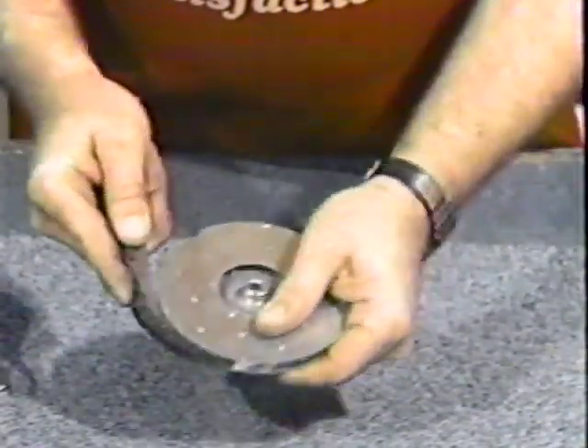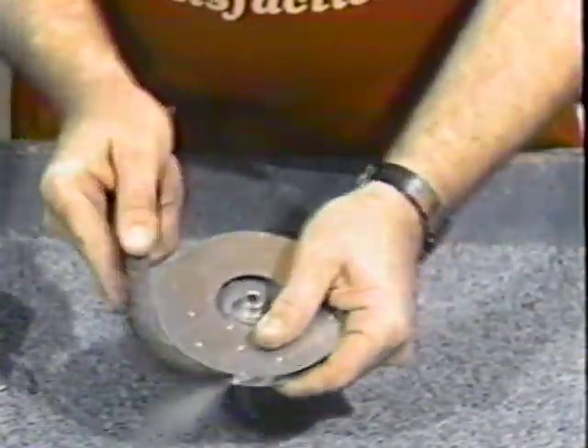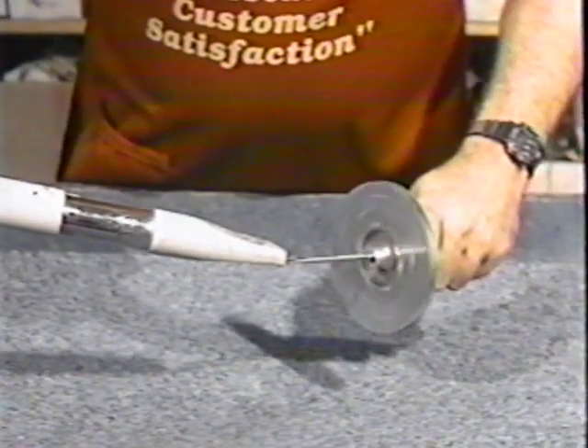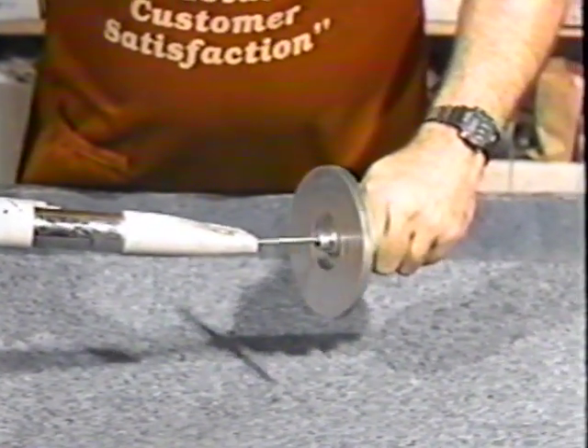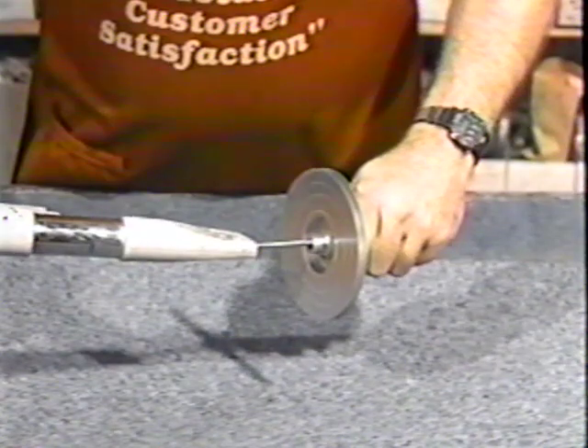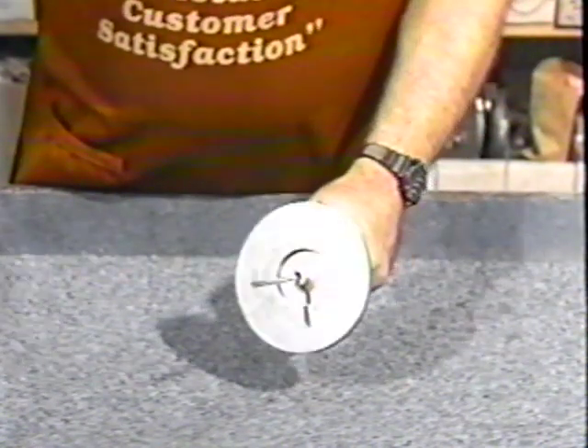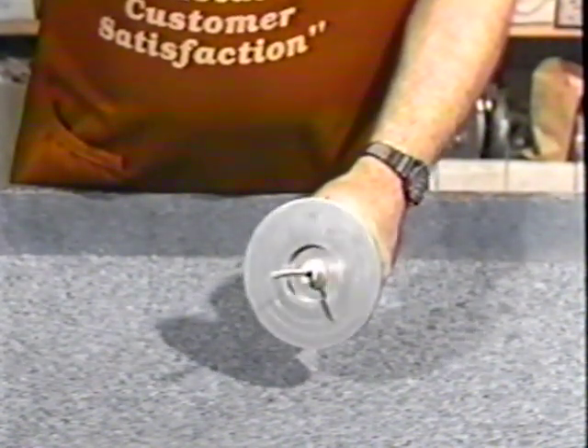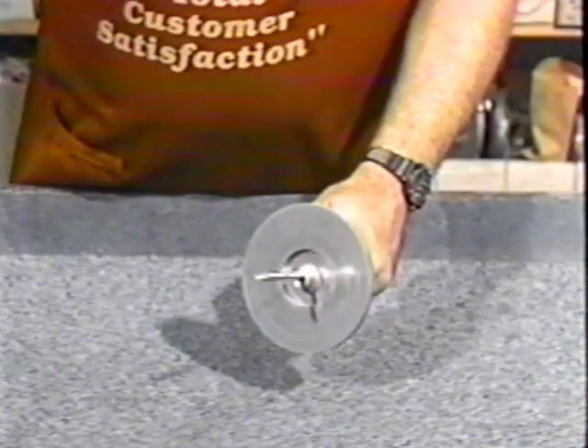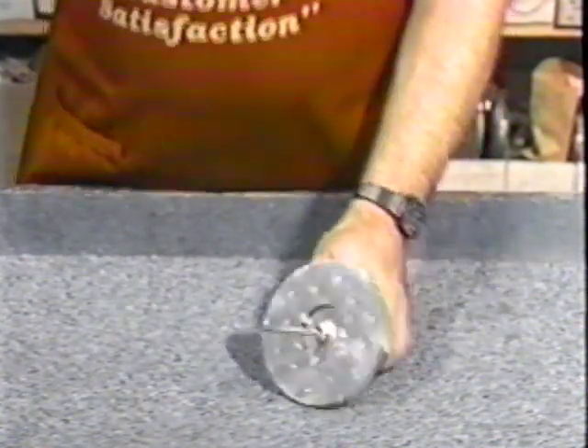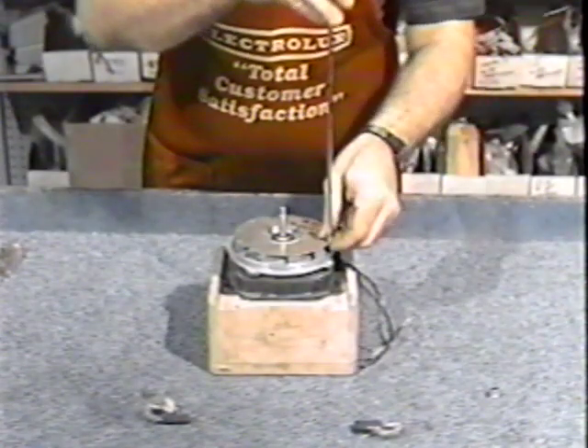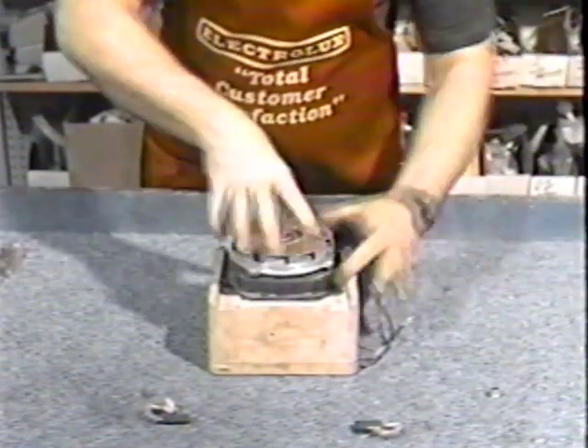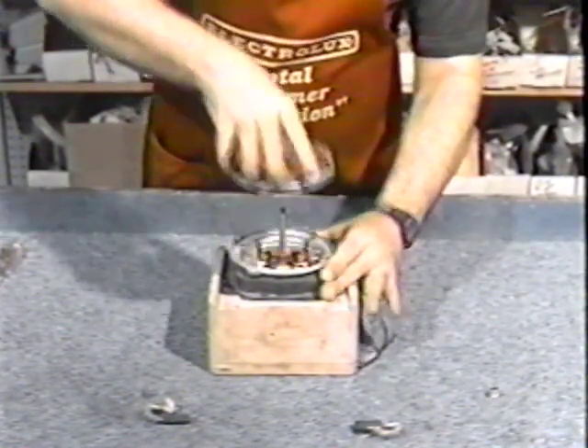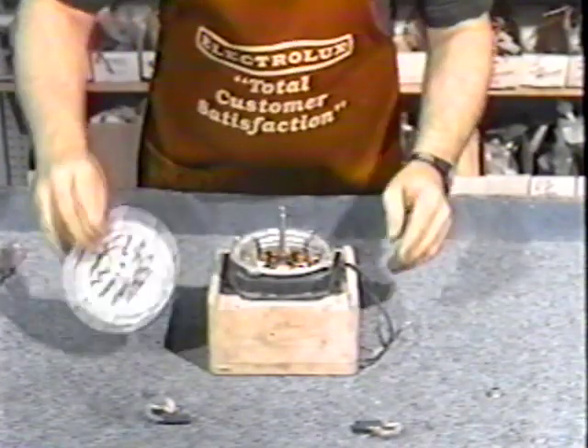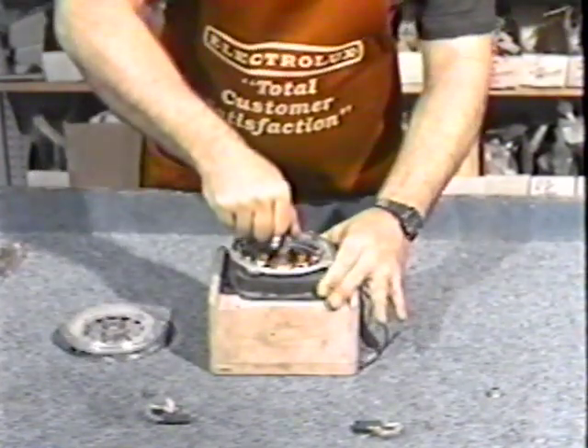Now clean the diffusers and fans with a small brush strip. To check for balance, place the fan on a screwdriver, blow air to spin the fan, and examine for the amount of wobble. If not true, the fan is out of balance and should be replaced. Motor disassembly is completed by removal of the 3 retaining screws, the fan end bracket, and the armature.